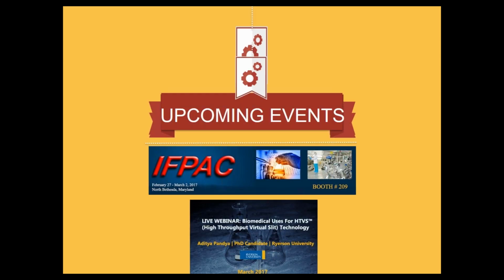One of our engineers should, of course, speak on this even more so, but there is this relationship in both engineering and spectroscopy of going to different laser frequencies. You can go to a shorter excitation wavelength, like 532. You get more photon scatter, which means you could have a faster signal and faster acquisition times. The problem there, you get far more things that are fluorescent. You can go the other direction to 1064 that could produce far less fluorescence, but then you get lambda to the -4th power less photon scatter, so there's far less signal.